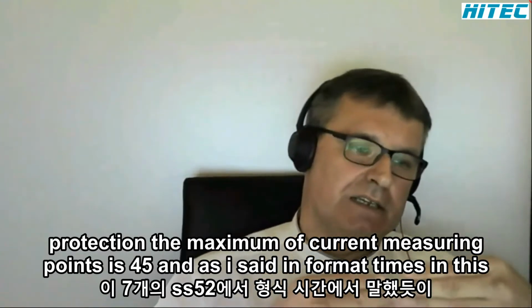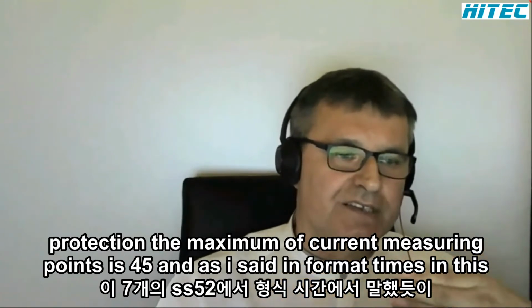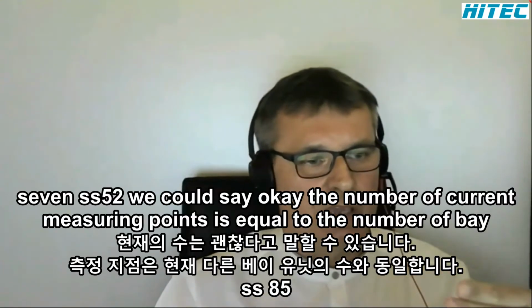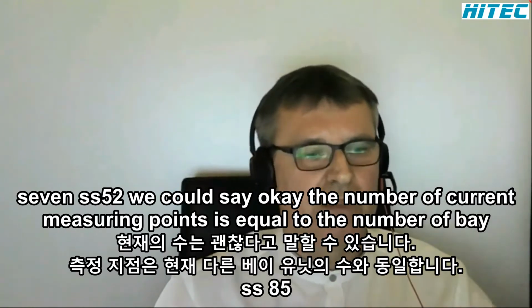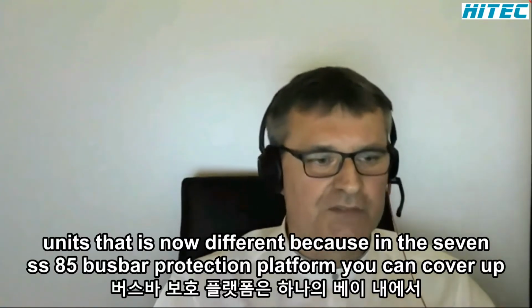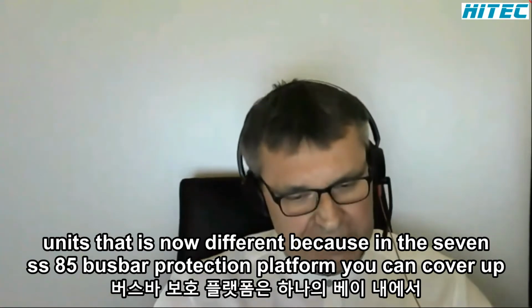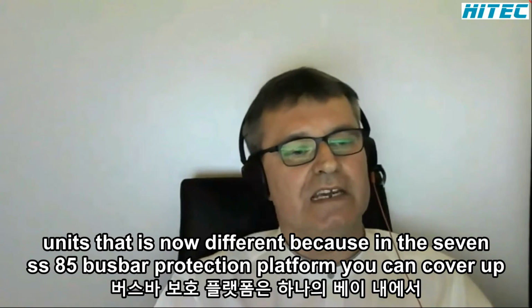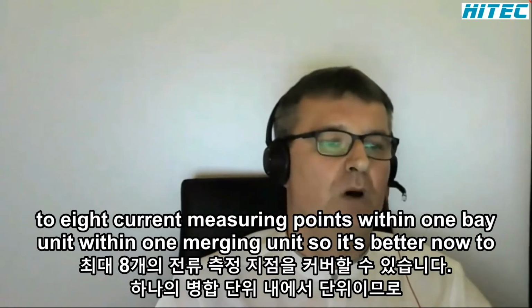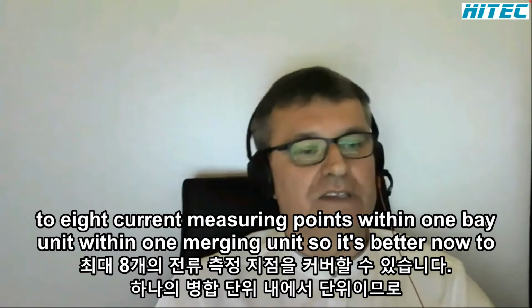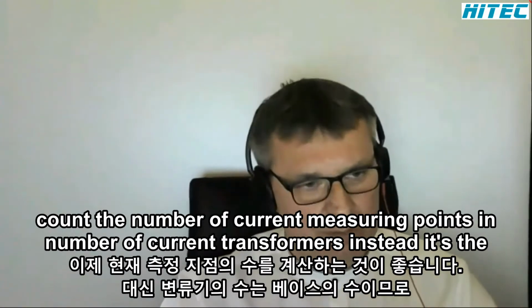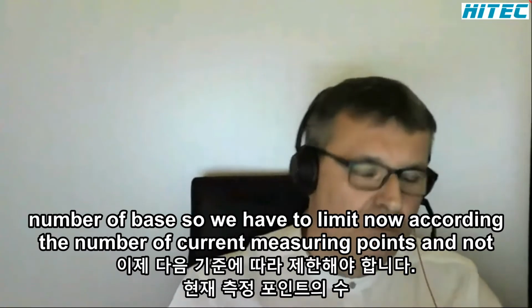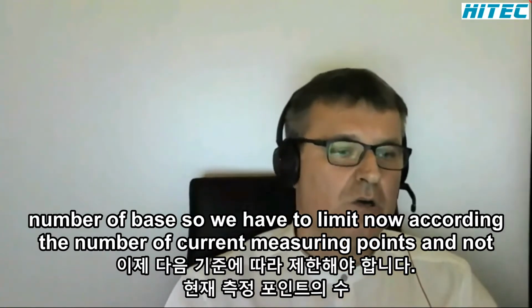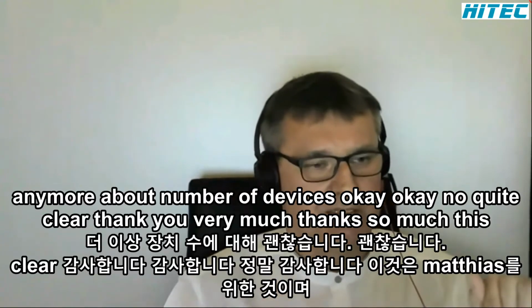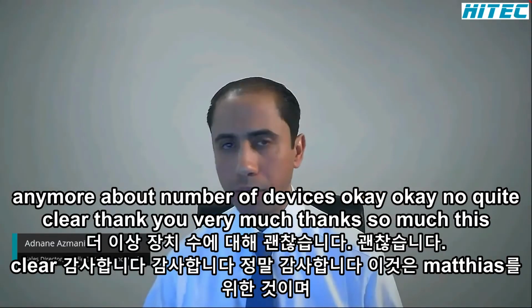As I said, in former times with the 7SS52, we could say the number of current measuring points is equal to the number of bay units. That is now different, because in the 7SS85 busbar protection platform, you can cover up to 8 current measuring points within one bay unit, within one merging unit. So it's better now to count the number of current measuring points, the number of current transformers, instead of the number of bays. We have the limit now according to the number of current measuring points and not anymore the number of devices. Okay. Quite clear. Thank you very much.